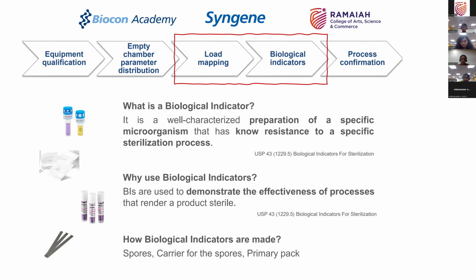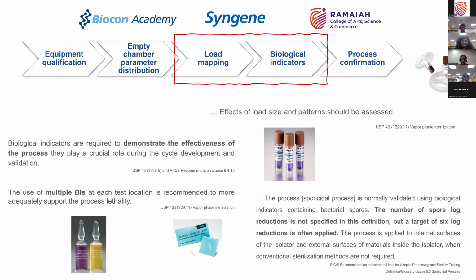What are biological indicators? We have already seen them in the past. A well-characterized preparation of a specific microorganism that has known resistance to a specific sterilization process. We had Bacillus stearothermophilus for autoclaves, Bacillus atrophaeus for dry heat sterilization, and so on. Such indicators are what is used. These are your friends. Please remember what you saw in the other one: in gamma irradiation, these cannot be used. So biological indicators are very good friends.